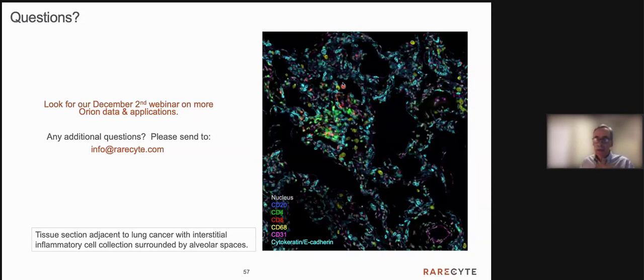The staining is also done in a single process — the entire slide is stained all at once, and after it's stained, it's scanned all at once. We do not use any iterative or cyclic process. This was very intentional. When you use an iterative process, it not only takes time, but it has issues regarding registration. And perhaps more importantly, if you have to erase the stain each time, it can have an effect on the antigenic preservation of the epitopes that the antibodies are used to identify. So those were specifically things we wanted to design out — to preserve the antigens, simplify the staining process, and increase the speed of scanning.